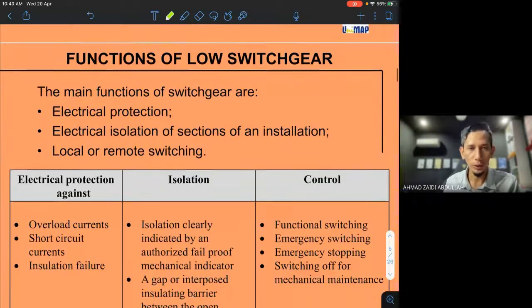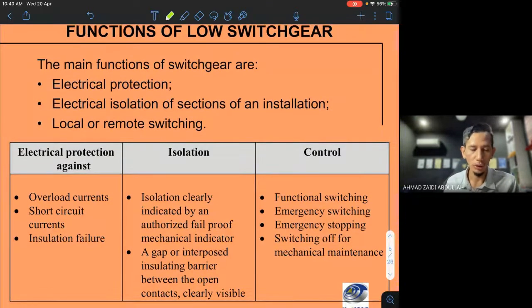Okay, next. So this table shows the function of the switchgear. So normally we separate into three. Yeah. So number one is the protection. Okay, we design the switchgear in order to cover this protection function. So the protection is able to protect against overload, short circuit, and insulation failure. Normally, you need to design to cover all this protection. Okay, overload macam mana? So later we will cover how. Short circuit, macam mana, how does the condition of short circuit, and then insulation failure. So how to protect if the cable is broken or failed. So how are we going to design it? That's macam tu.